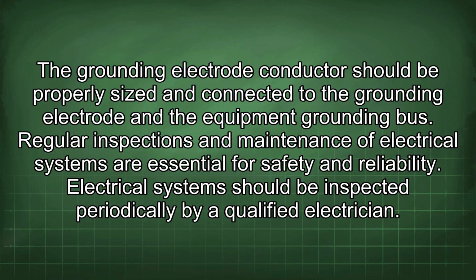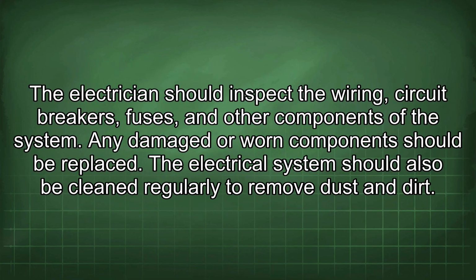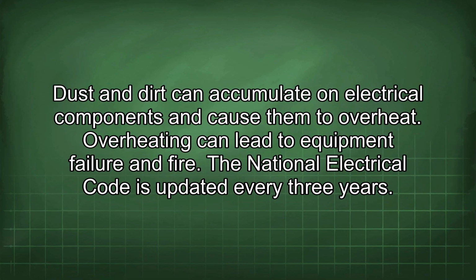Regular inspections and maintenance of electrical systems are essential for safety and reliability. Electrical systems should be inspected periodically by a qualified electrician. The electrician should inspect the wiring, circuit breakers, fuses, and other components of the system. Any damaged or worn component should be replaced. The electrical system should also be cleaned regularly to remove dust and dirt. Dust and dirt can accumulate on electrical components and cause them to overheat. Overheating can lead to equipment failure and fire.